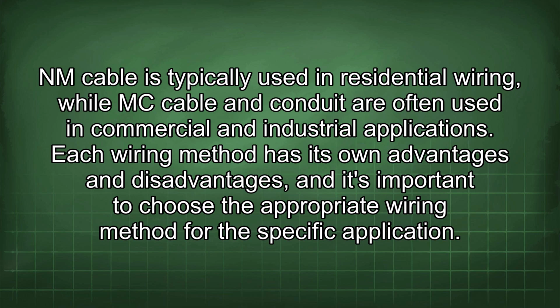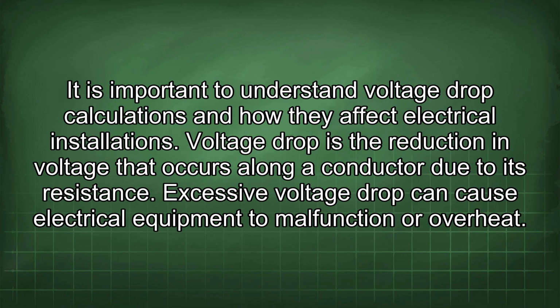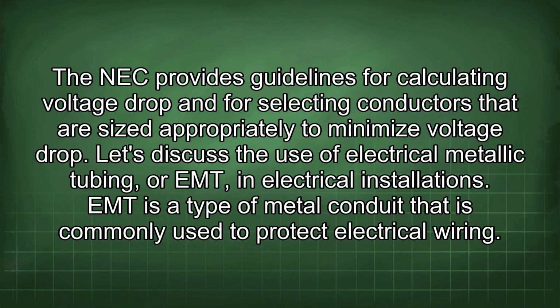the specific application. It is important to understand voltage drop calculations and how they affect electrical installations. Voltage drop is the reduction in voltage that occurs along a conductor due to its resistance. Excessive voltage drop can cause electrical equipment to malfunction or overheat. The NEC provides guidelines for calculating voltage drop and for selecting conductors that are sized appropriately to minimize voltage drop.